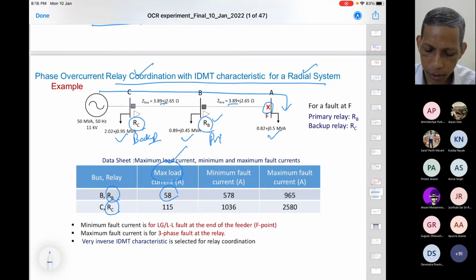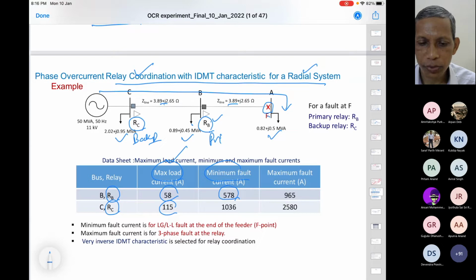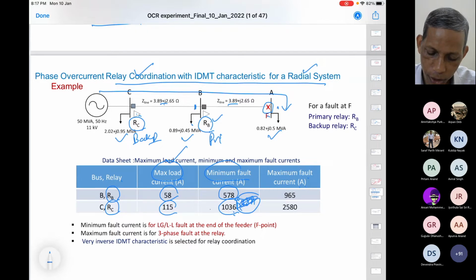58 is observed by RB, 115 is observed by this one. So there is some load here, so both loads are added in this. The minimum fault current for RB is nothing but at F, the remote point, the farthest point. So 578, phase-to-phase fault. And for the corresponding RC, the minimum fault current considered is about 1036. Actually, this minimum fault current for RC should also cover from here to here. So this will also be 578 ampere. Agree? Maximum fault current for A, this is our bus level. Agree? Bus relay. So this, sorry, this is not correct. This is 1036. If we create a fault here, it will be 578.